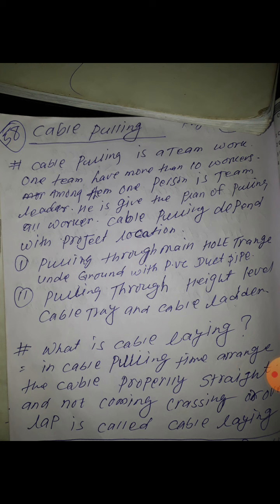During pulling time you should check your area, in the cable tray area there may be some overlapping or crossing, you can arrange this, remove the cross and overlap. If you make an overlap and don't complete removing the crossing, this means it is not accepted. You should be clear about this.